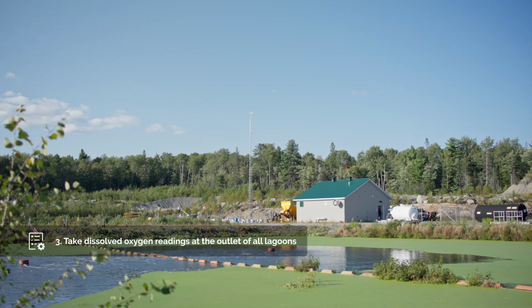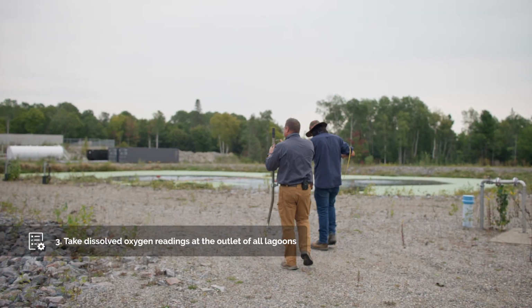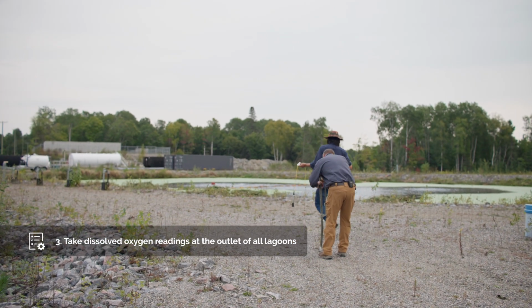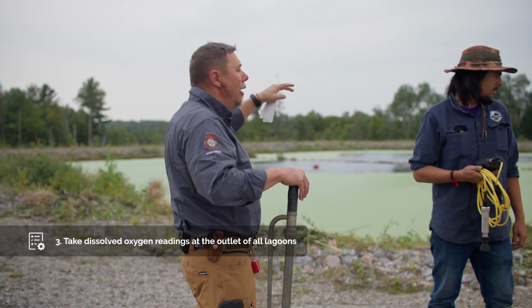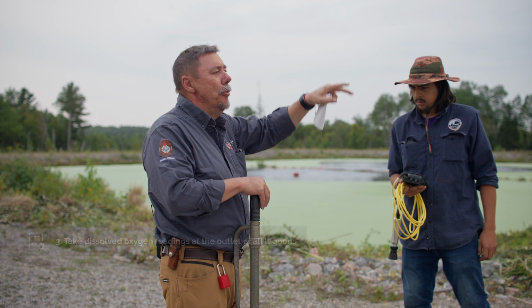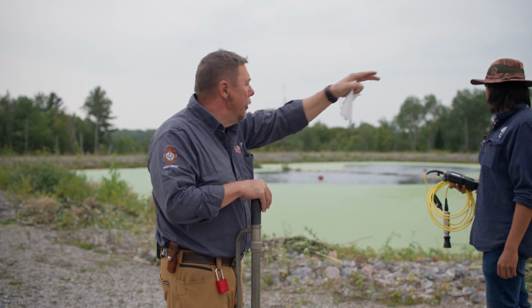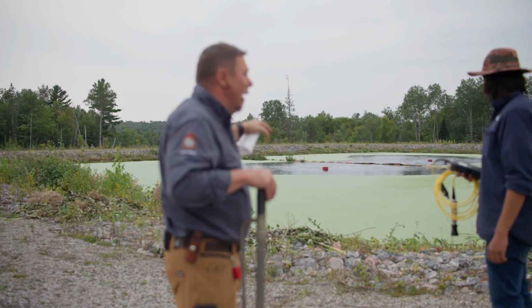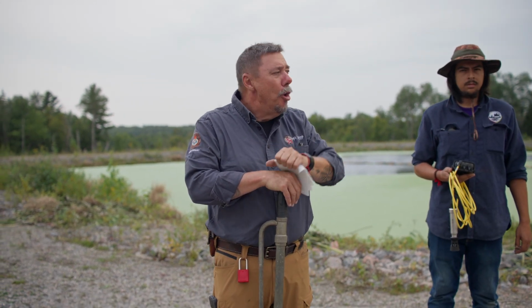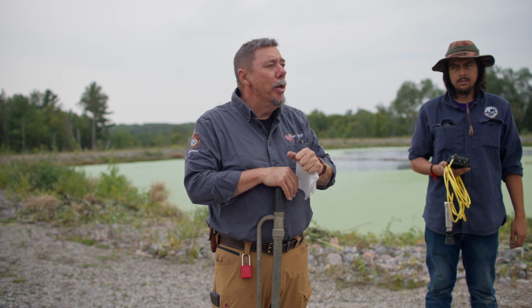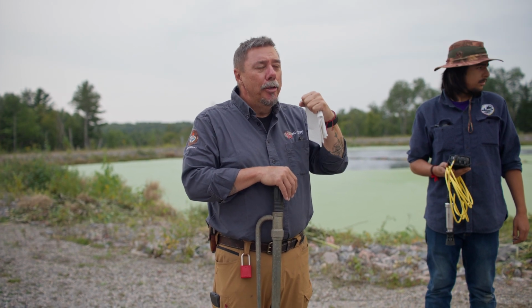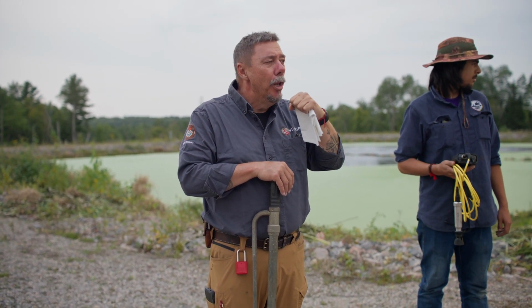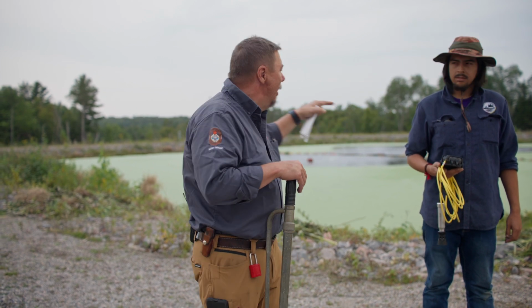Here in Quebec, we have aerated lagoons. They're very friendly for vegetation. We have 2 lagoons with 2 cells in each. So we have cell number 1, cell number 2, cell number 3, and cell number 4. It's very important for dissolved oxygen that we have at least 2 milligrams per liter throughout the lagoons. We know that the pollutant load is heavier in lagoons 1 and 2 than it would be in 3 and 4.